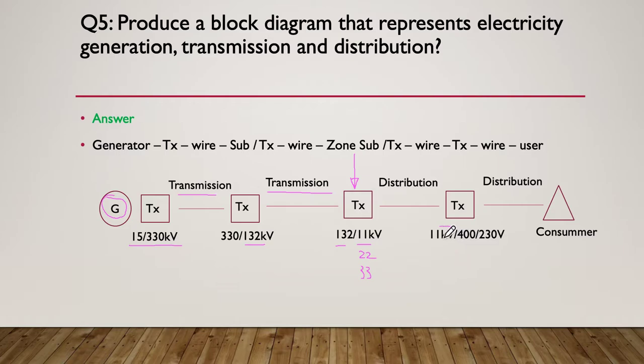Normally at 11 kV. And then you've got pole mount transformers and kiosk transformers. Then reduce the voltage back down to 400 and 240 volts which in turn is provided to our final customer. And those last two steps is called distribution.